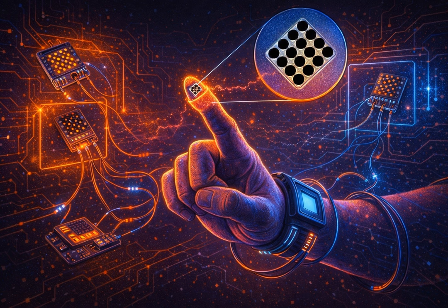Tell us about that. The current intensity, the pulse height, can be delivered per channel from 0 up to 3.8 milliamps, and it's incremented in 200 distinct steps of 19 microamperes each. That is an extremely granular resolution. Why is that so important? It's crucial because it allows the software to create what feels like an imperceptibly smooth change in sensation. So the user experiences a slow fade or a ramp up, not a series of jarring on-off stages.